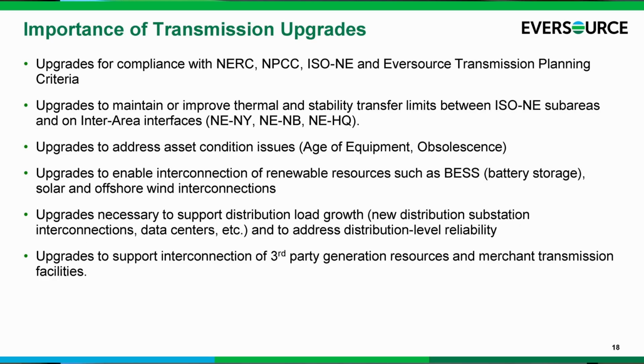Next I'll go to the slide about specific projects involving transmission upgrades to support distribution load growth. To the extent additional capacity is needed, oftentimes a new substation is needed. Distribution planning identifies the capacity needed and roughly the area of the station. Then transmission planning steps in to figure out how to connect that station into the network, so power flows to transmission, then to the substation, then eventually into the distribution load.